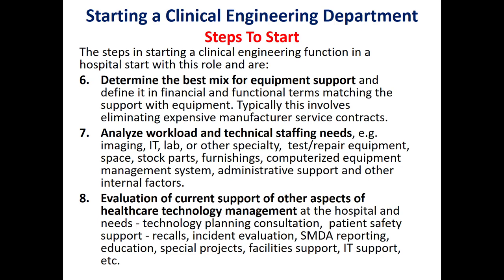We then make an evaluation of the maintenance. Clinical engineering services include maintenance and other services. The other services include technology planning consultation, patient safety support, recalls, incident evaluation, SMDA reporting, education and training for staff, sharing in special projects, facilities support, IT support, and so on. So the clinical engineering service is made up of two parts: maintenance and these other services.